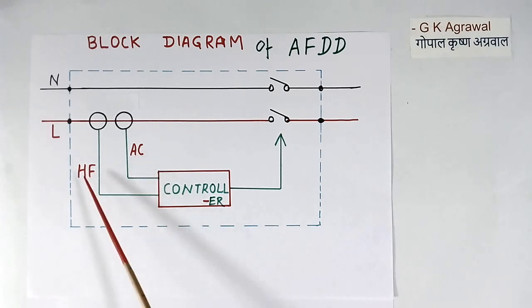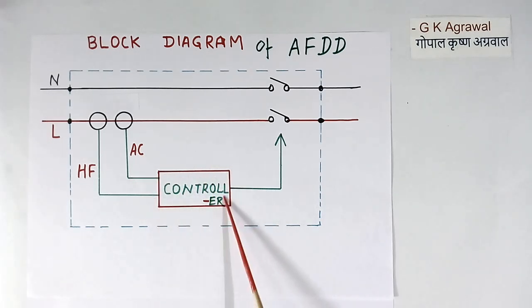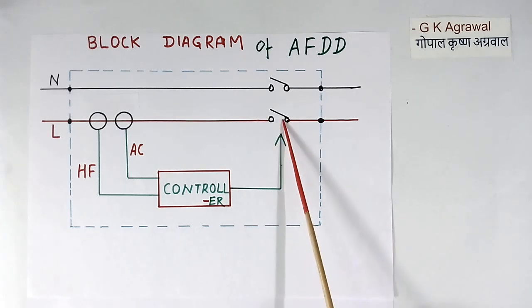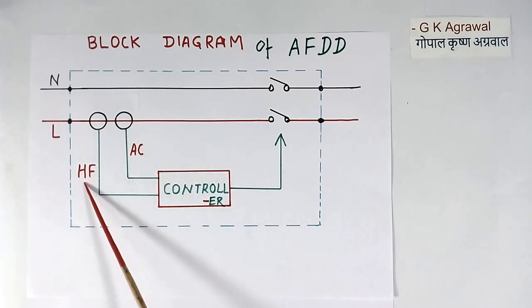This arc produces high frequency current in the wire. These two currents, high frequency and normal AC current, go to controller. Controller will process it, and if required, it will trip using an MCB. There will be MCB inside also. So this way it senses the arc by sensing high frequency current, and trips the system as per requirement.